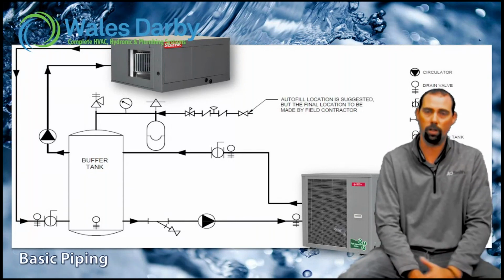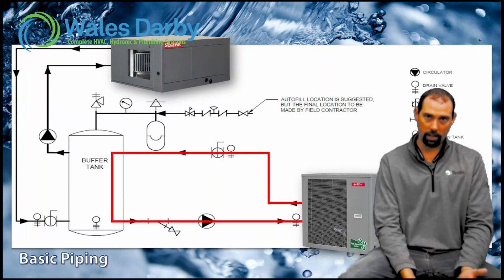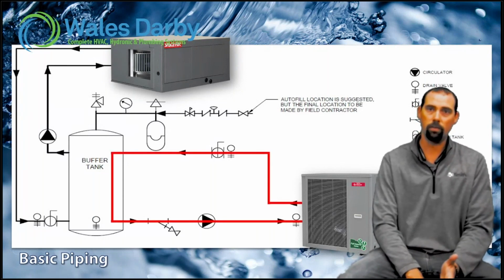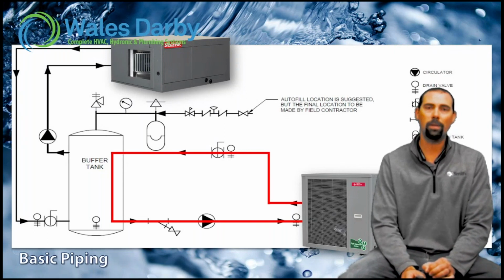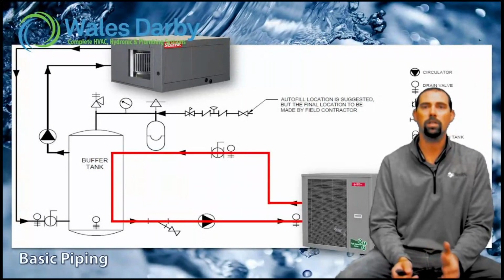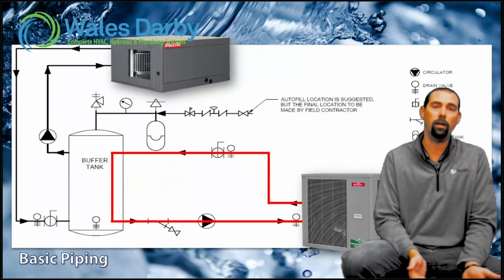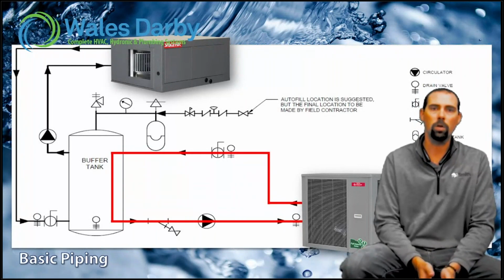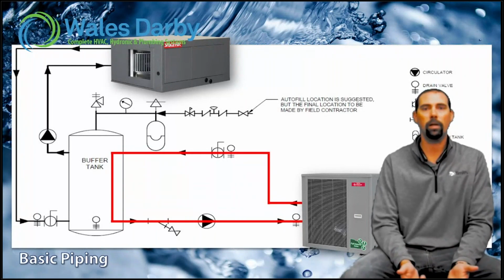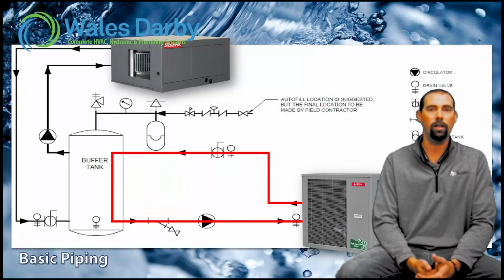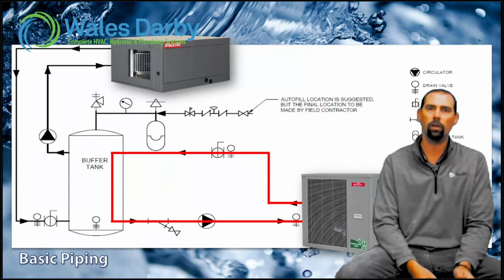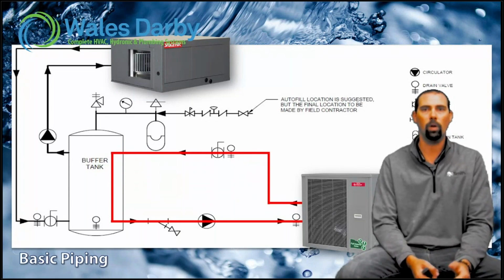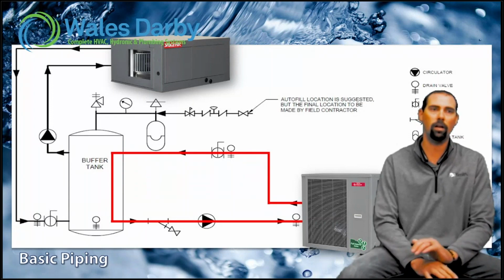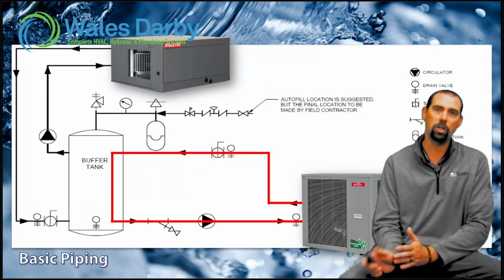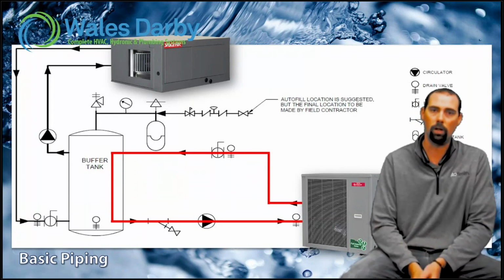But we really have two systems here. To break it down, we have our heat pump side. All that heat pump cares about is maintaining a certain temperature in that buffer tank that we set - just like any other storage tank. It doesn't care what zone's calling, how many zones you have, or what temperature the zones are. None of that comes into play. The heat pump just cares about what that buffer tank wants.